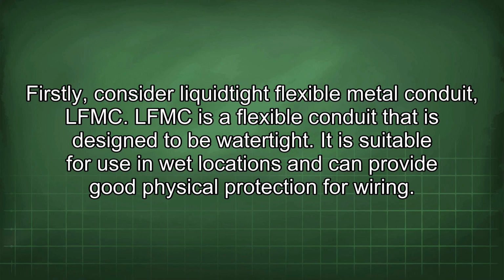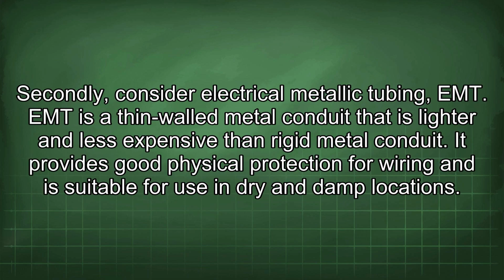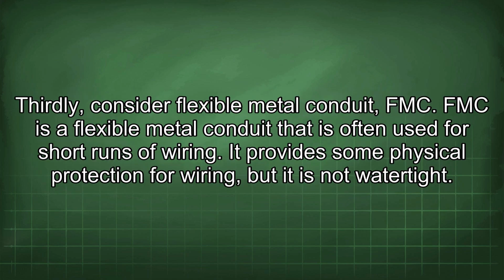Firstly, consider liquid-tight flexible metal conduit (LFMC). LFMC is a flexible conduit that is designed to be watertight. It is suitable for use in wet locations and can provide good physical protection for wiring. Secondly, consider electrical metallic tubing (EMT). EMT is a thin-walled metal conduit that is lighter and less expensive than rigid metal conduit. It provides good physical protection for wiring and is suitable for use in dry and damp locations. Thirdly, consider flexible metal conduit (FMC). FMC is a flexible metal conduit that is often used for short runs of wiring. It provides some physical protection for wiring, but it is not watertight.